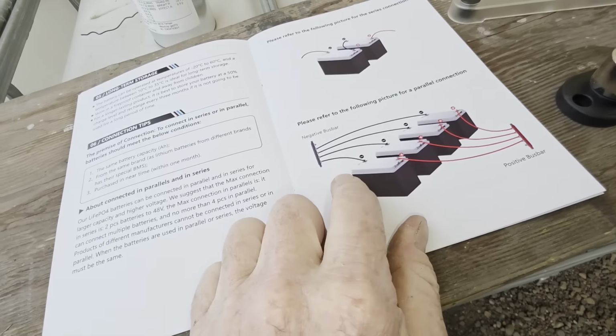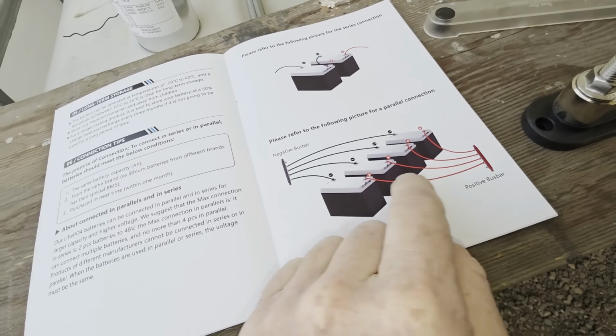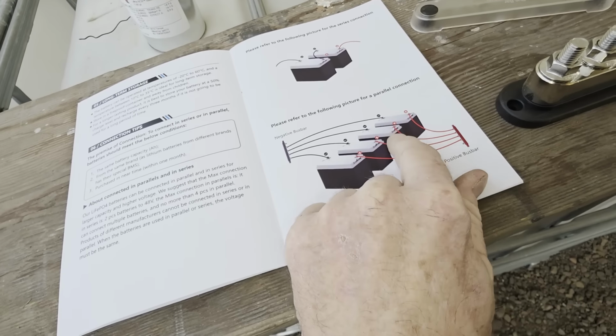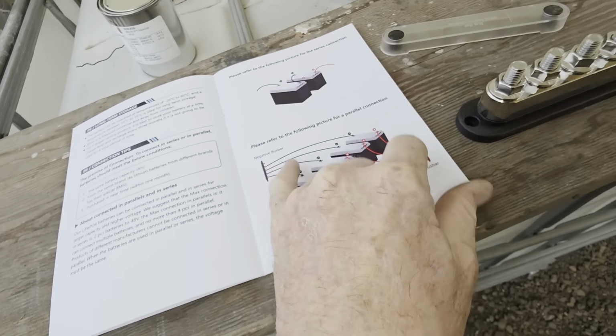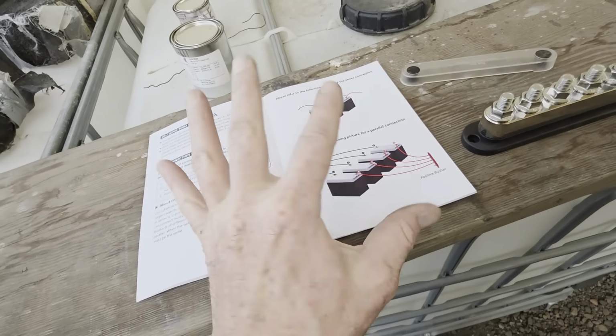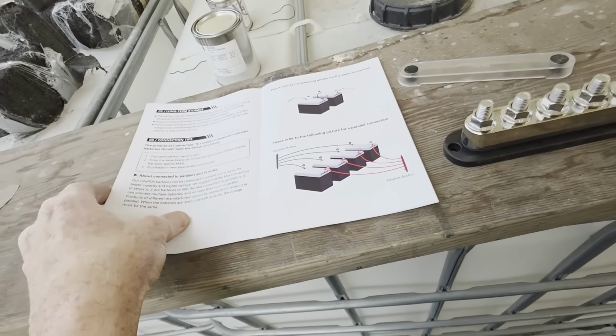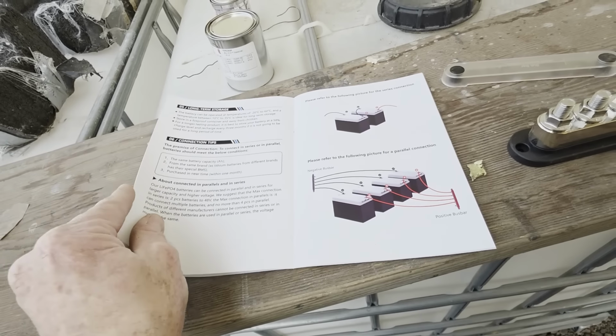One thing you might also want to recognize is that they do recommend that all the leads coming from the batteries to the bus bar are the same length. That way we keep all the batteries in optimal balance, because the leads won't be any different in length, because that can affect the resistance of the cables, of the conductor itself.